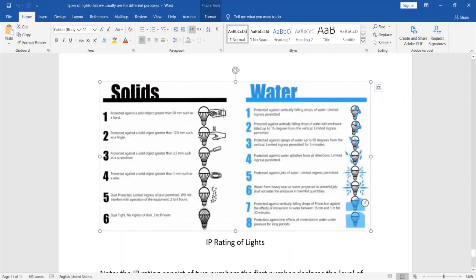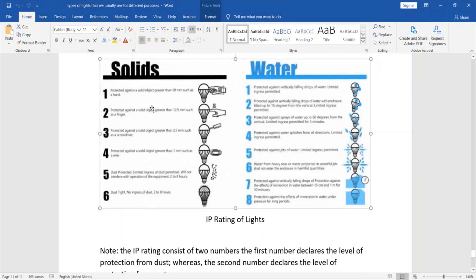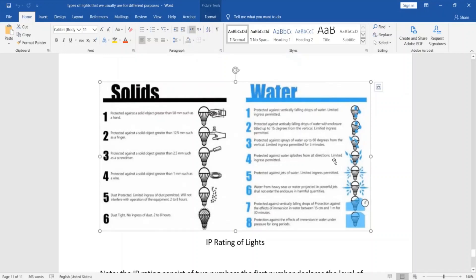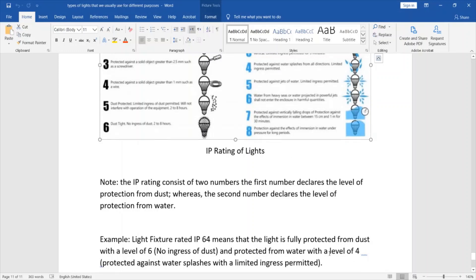This diagram shows the IP rating of lights. The IP rating consists of two numbers: the first number declares the level of protection from solids or dust, whereas the second number declares the level of protection from water. The protection from solids ranges from level one to level six, and water protection ranges from one to eight. For example, a light fixture rated IP64 means it is fully protected from dust — level six means dust-tight with no ingress — and has level four water protection, which means protected against water splashes with limited ingress permission.